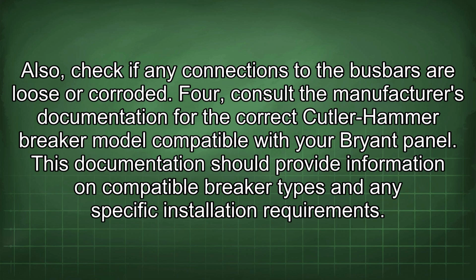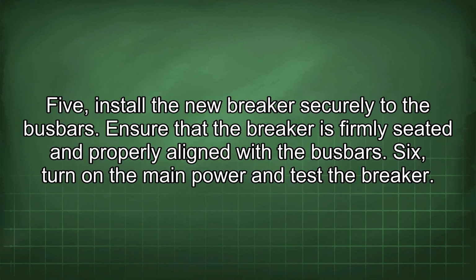4. Consult the manufacturer's documentation for the correct Cutler-Hammer breaker model compatible with your Bryant panel. This documentation should provide information on compatible breaker types and any specific installation requirements. 5. Install the new breaker securely to the bus bars. Ensure that the breaker is firmly seated and properly aligned with the bus bars.